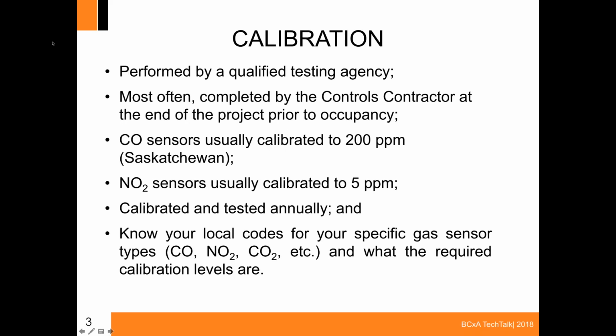So the calibration of these pieces of equipment, these sensors, is usually performed by a qualified testing agency, but more often than not, prior to substantial completion, we see it's the controls contractor that is doing it at the end of the project, since they're typically the ones supplying the sensors, whether they're getting them through Honeywell or some other company that provides them. We calibrate them usually to about 200 ppm for the CO and 5 ppm for the NO2, and that's typically what we see in Saskatchewan for parkades.